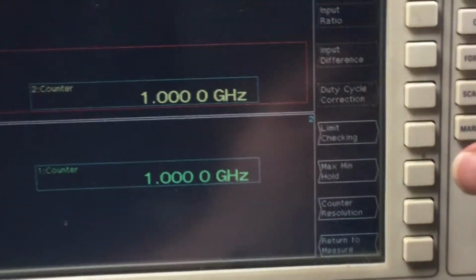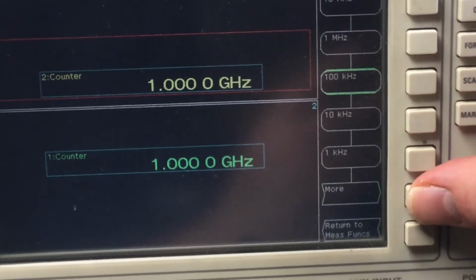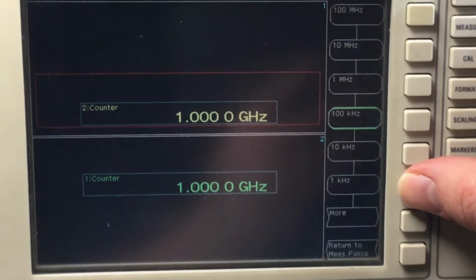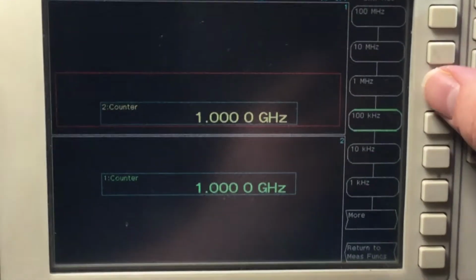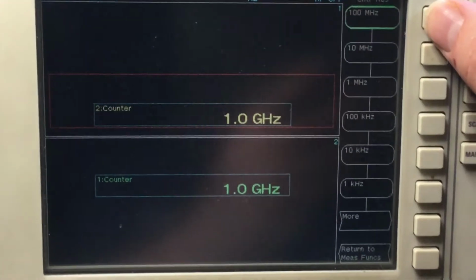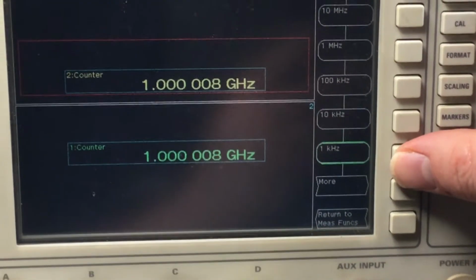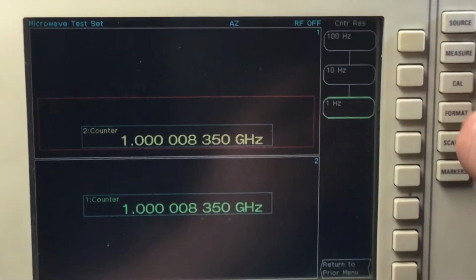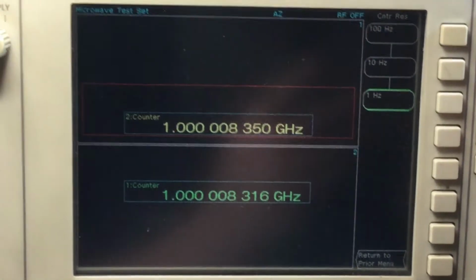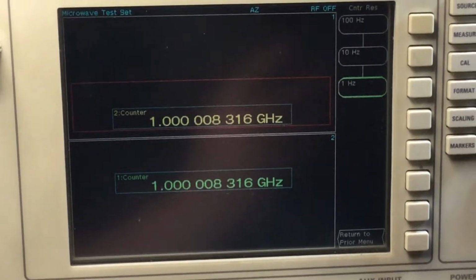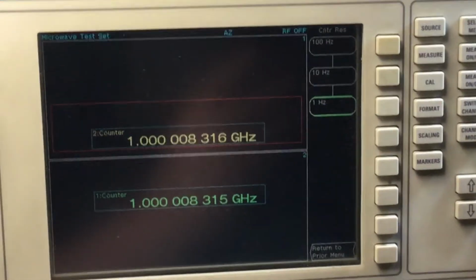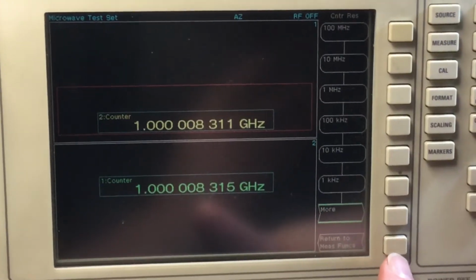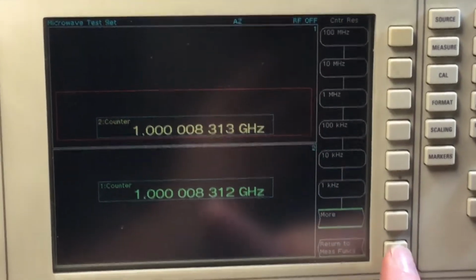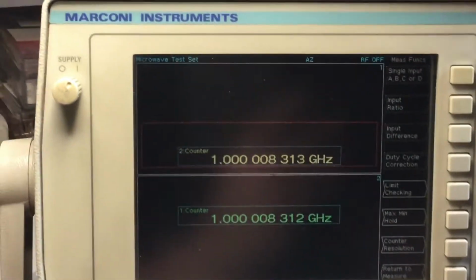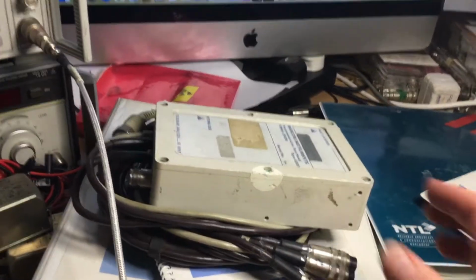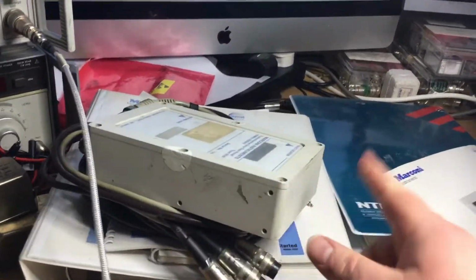So if we go to, I think it's counter resolution, you've obviously got all these, so you can set it up to 1 kHz, 10 kHz, 100 kHz, 1 MHz, 10 MHz, and then 100 MHz, and I think there's more in 1 Hz as well, down to 1 Hz. So that's how accurate it is, really, very accurate indeed, with a number of decimal places that it can read. So that gives you a little rundown of the frequency counter operation, and then I'll just show you the detector head now, which I've got. I'll connect this up, which is for fault location as well. I'll put that on next.